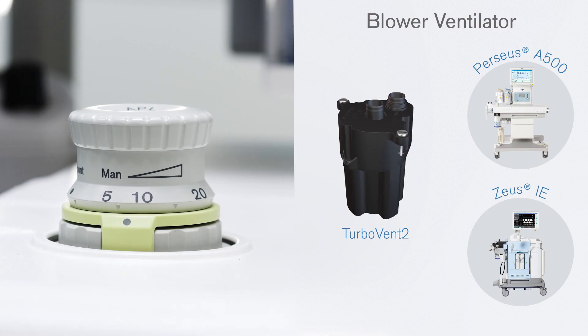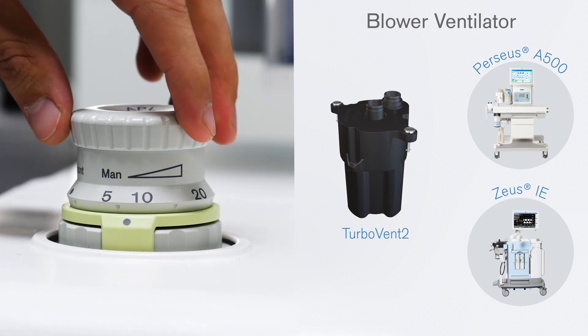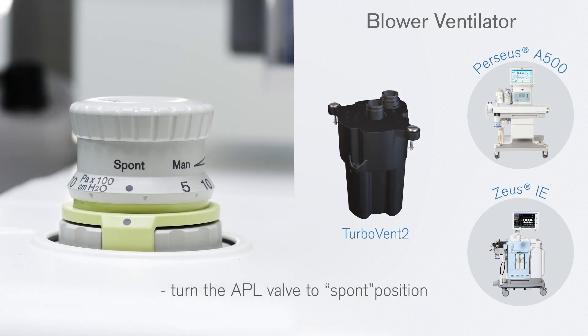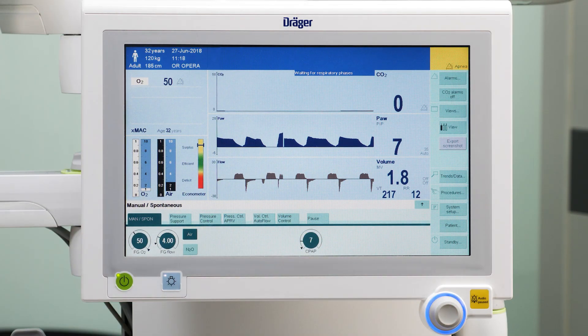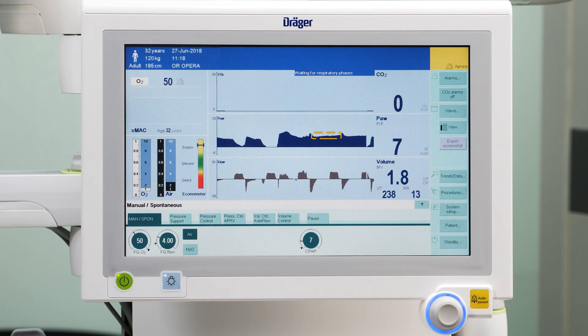Instead of this method, with the Draeger anesthesia machines Zeus IE and Perseus A500, which have a blower ventilator, the TurboVent-2, an active CPAP can be applied without interruptions during pre-oxygenation and recovery, where a continuous flow actively counteracts the intrinsic PEEP and thus reduces the work of breathing. The blower can adjust its speed extremely quickly to react to any pressure changes and maintain the set pressure during spontaneous breathing.